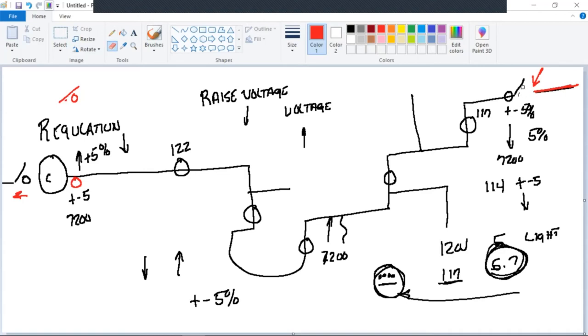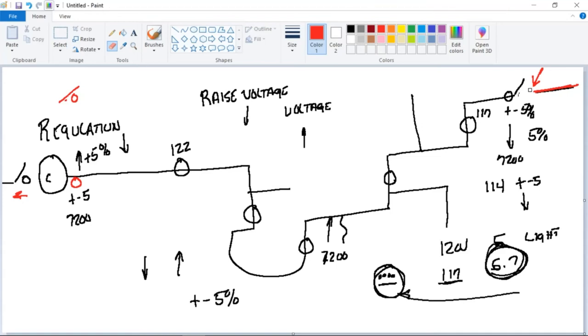Is that a common thing? I wouldn't say common. It happens. And you've got to think, a voltage regulator, through SCADA and through on-site observations, counts how many times it had to change steps or how many times it had to regulate voltage. And after a certain amount of steps or regulation changes, it's going to have the oil changed to be maintained. So yeah, it does happen.